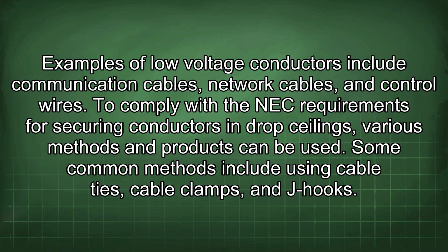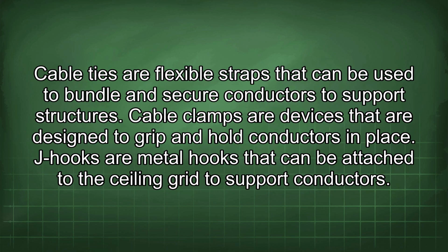To comply with the NEC requirements for securing conductors in drop ceilings, various methods and products can be used. Some common methods include using cable ties, cable clamps, and J-hooks. Cable ties are flexible straps that can be used to bundle and secure conductors to support structures. Cable clamps are devices that are designed to grip and hold conductors in place. J-hooks are metal hooks that can be attached to the ceiling grid to support conductors.